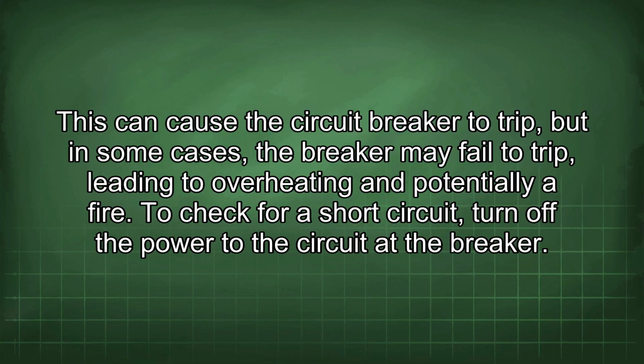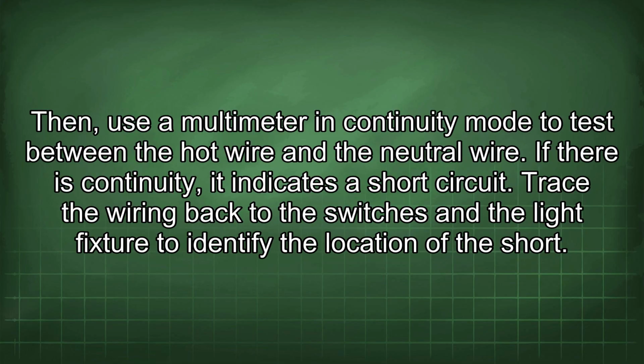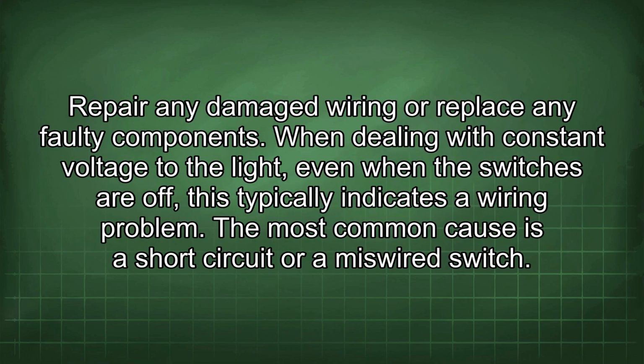To check for a short circuit, turn off the power to the circuit at the breaker. Then, use a multimeter in continuity mode to test between the hot wire and the neutral wire. If there is continuity, it indicates a short circuit. Trace the wiring back to the switches and the light fixture to identify the location of the short. Repair any damaged wiring or replace any faulty components.